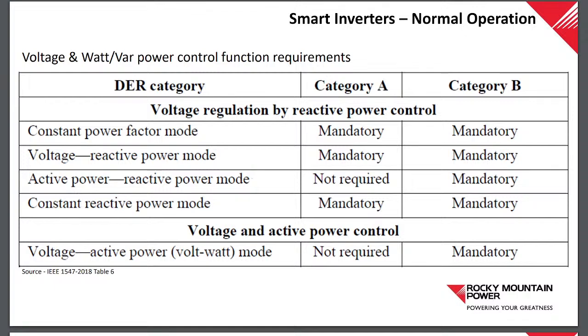They don't have the capability for voltage regulation, right? So we don't have the ability to fluctuate the VARs to match, like if we have high voltage, to reduce the voltage, and if it's low voltage, raise the voltage, because it's set at unity power factor. So unity power factor, there's no VAR support, it's just constant. So if you need to push power back, you've got to raise the voltage a little bit. That's why you're seeing a lot of the high voltage issues with high penetration of generation.